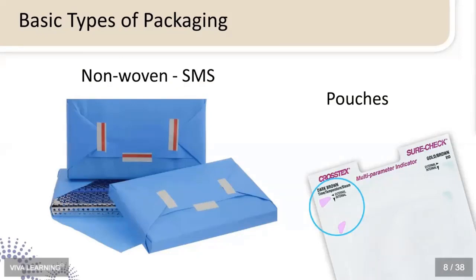These items are reusable, but they do require laundering. It's not like you can just keep using them over and over again. You need to follow the IFU from that textile manufacturer. They have to be delinted and inspected for holes and any type of degradation of the fabric. The recommendation is to use a light table if you are using a reusable textile. So inspection and mending of holes and defects are important. It's also a bit time consuming, which is why we tend to prefer the disposable options of single-use pouches and single-use non-woven wraps.